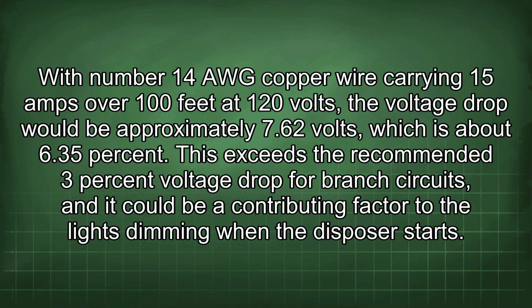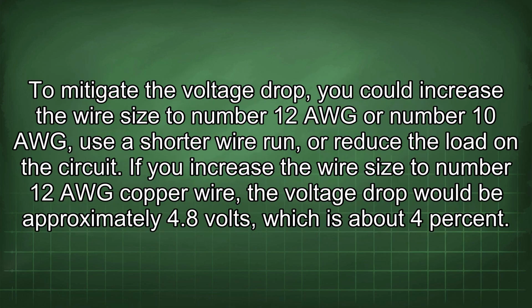This exceeds the recommended 3% voltage drop for branch circuits, and it could be a contributing factor to the lights dimming when the disposer starts. To mitigate the voltage drop, you could increase the wire size to number 12 AWG or number 10 AWG, use a shorter wire run, or reduce the load on the circuit.